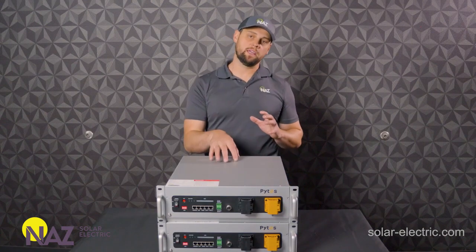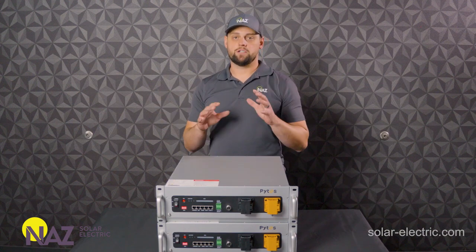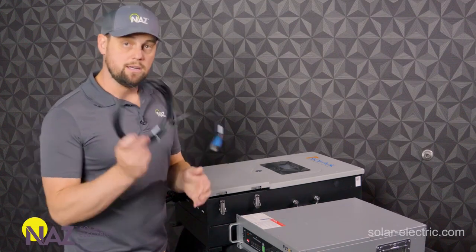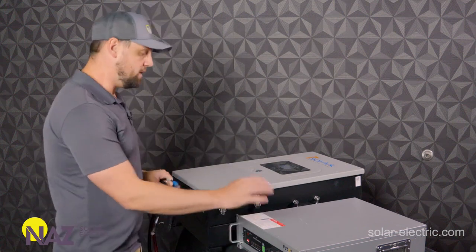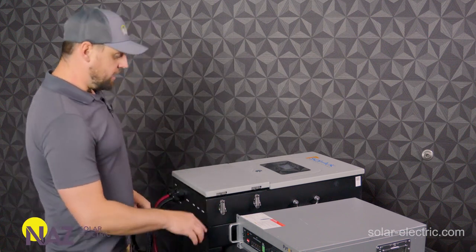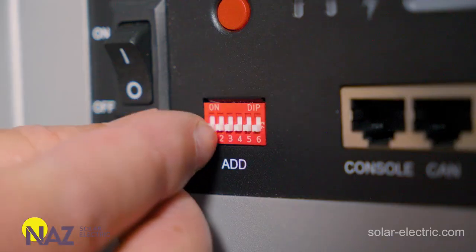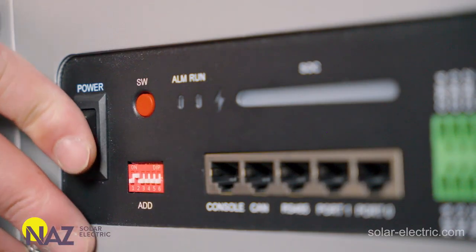Just to show you how easy it is to set up closed-loop communications with these Pytes batteries, we're going to connect one of these batteries up to a Sol-Ark inverter and show you how simple it is. You're going to need a dedicated UTP cable with the correct pinout for communications between the Pytes battery and the Sol-Ark — we can provide you with this cable. What you're going to do is adjust the dip switch so that the communications protocol between Sol-Ark and Pytes is recognized. Take the second dip switch and put it up. That simple — that's all you've got to do with the battery, besides turn it on. We're going to go ahead and turn this battery on.